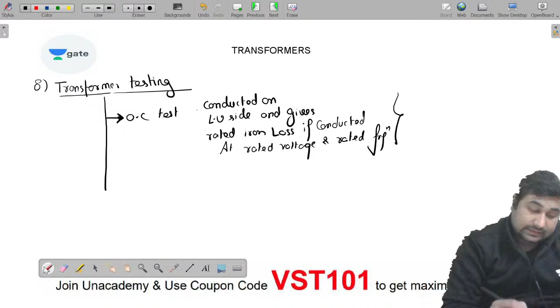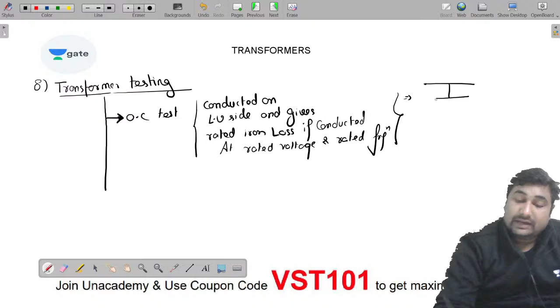You said sir, from here we have to remember one more thing, the electrical model and how to calculate the parameters. During open circuit test, we get RC and XM. It is easy to recall: the voltage applied is VOC, the power flowing into the transformer under open circuit test is POC, and the current is I0. This I0 is further divided into IC and IM. Now the rest is only KVL, only basic network analysis. I2 dash is 0. So we can easily find RC by voltmeter reading, ammeter reading, and wattmeter reading. Then we can find IC, then IM, and XM. I am hoping up to this everything is okay.